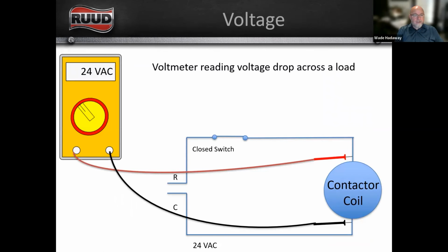So here we've got our meter. It's set to 24 volts, set to alternating current. Here's my contactor coil. I've got my closed switch, so I have energized my contactor coil, and I'm measuring on either side of that coil on my contactor, and I'm reading 24 volts. So what that means is that I've got 24 volts at my contactor coil, and I'm reading a 24 volt drop across the coil. So that lets me know that my contactor coil is energized.